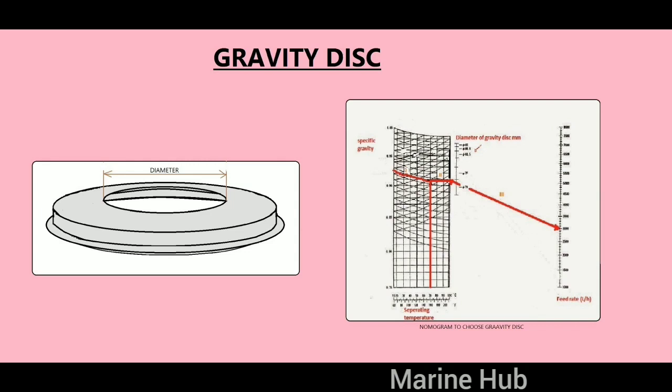The purifier is supplied with a number of gravity discs with different inside diameters. The optimum position of the interface is between the edge of the disc stack and outside edge of the top disc. This can be checked visually by looking at the underside of the top disc after running a few minutes.